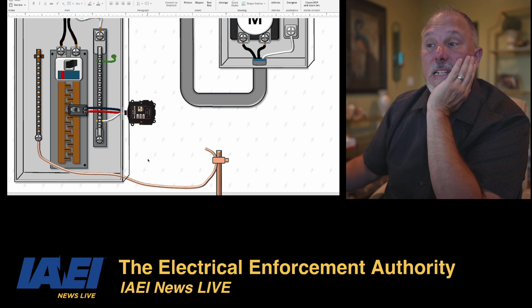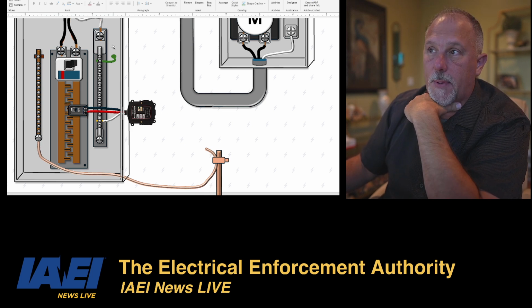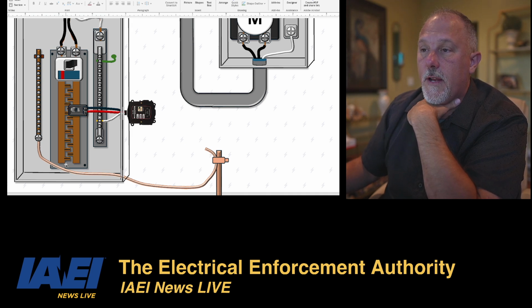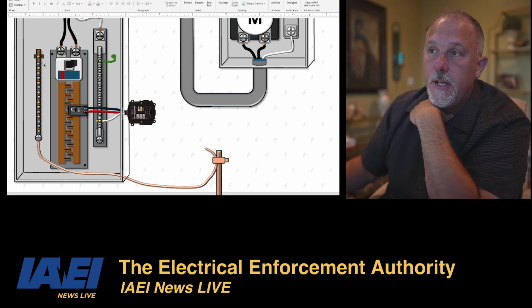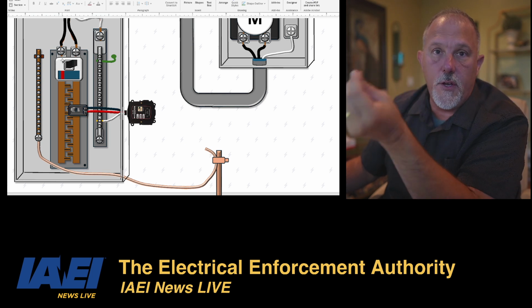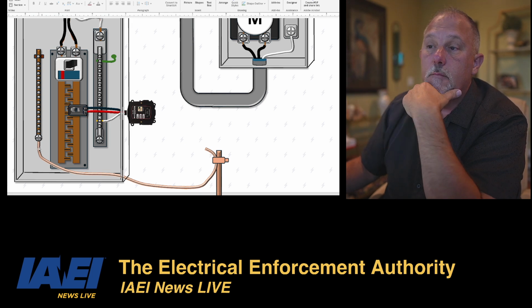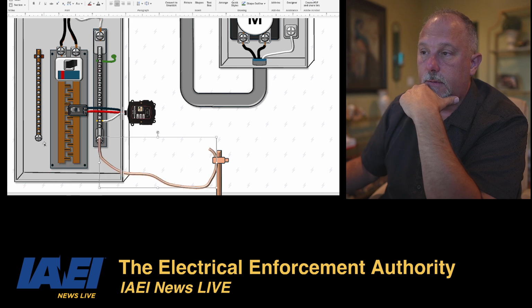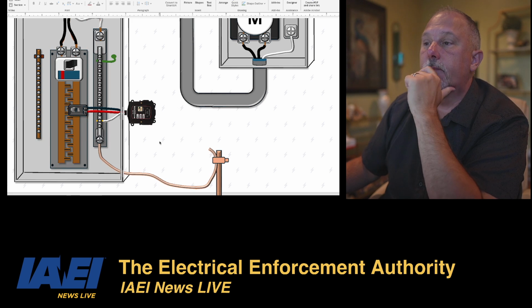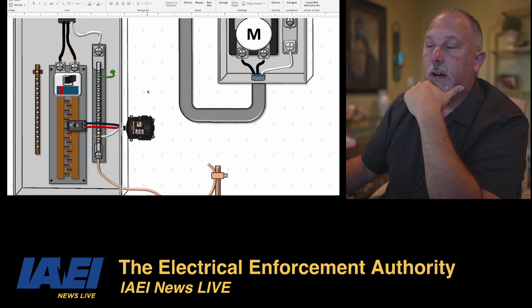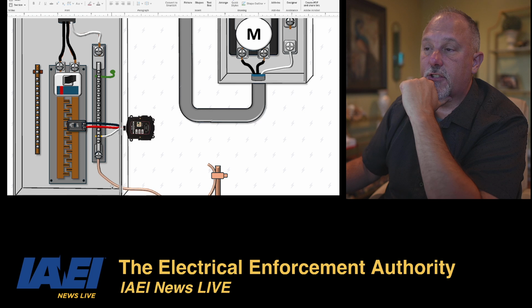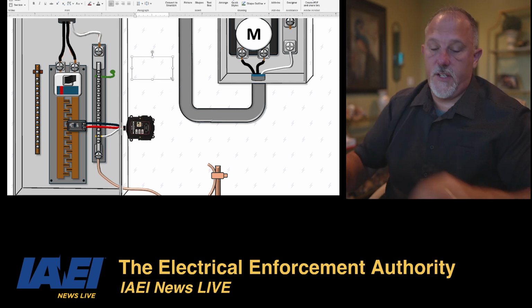All right, the reason I could not land my grounding electrode conductor on this is because I am using the back pan to connect the neutral bar with the grounding electrode conductor. So if I don't have this main bonding jumper being a wire or one of those types of solutions, then I must land this conductor right there. It has to be on that neutral bar. So I would have the grounded conductor coming in from the service, landing on the neutral bar. I would have my grounding electrode conductor landing on the neutral bar. And this could be bonded to the back pan, which would give me my main bonding jumper. So this would be my main bonding jumper.